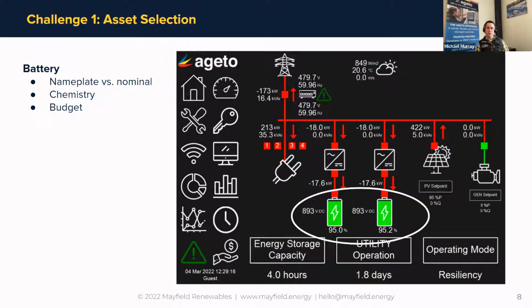Another key consideration on the batteries is their C rate, and that's how fast a battery can discharge its capacity. So in the energy storage space, they typically range from 2C down to 0.25 C. But the common ones are either 1C, which means you can fully discharge or charge the battery capacity in 1 hour, or 0.5 C, where the full discharge would take 2 hours. So that's one thing to look at.